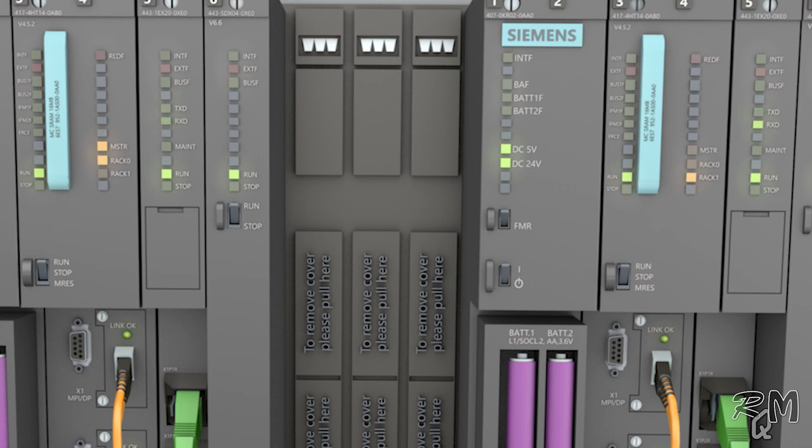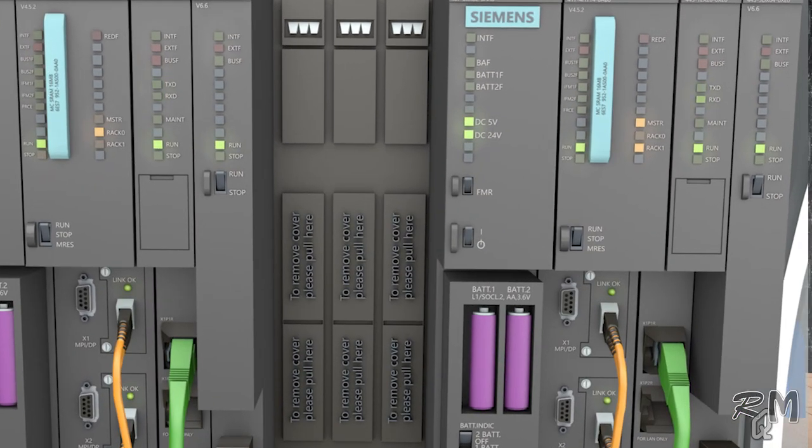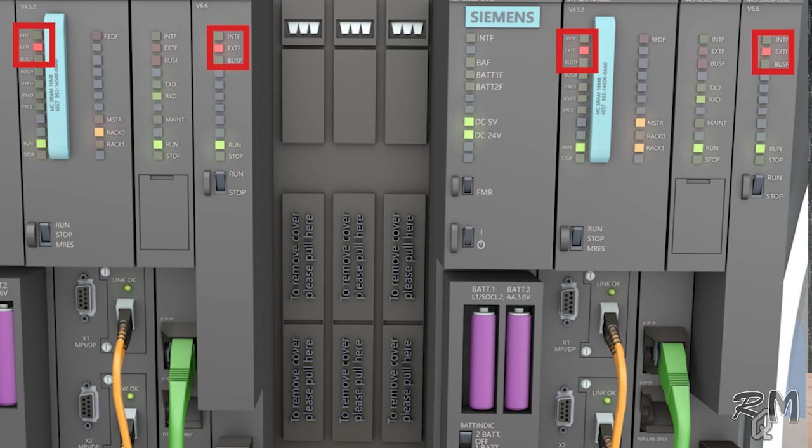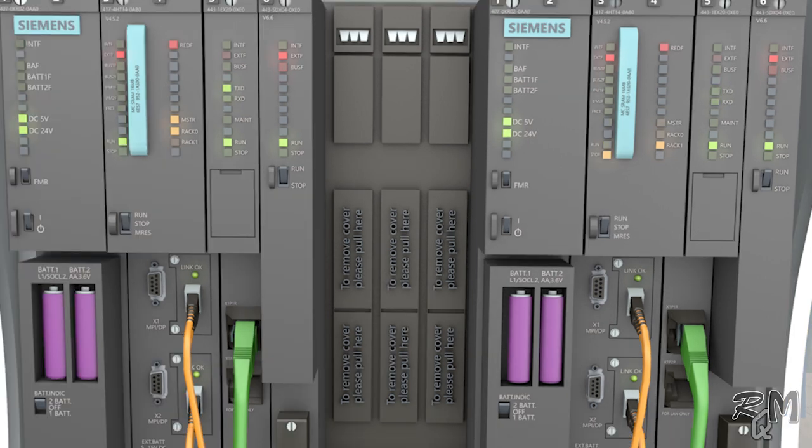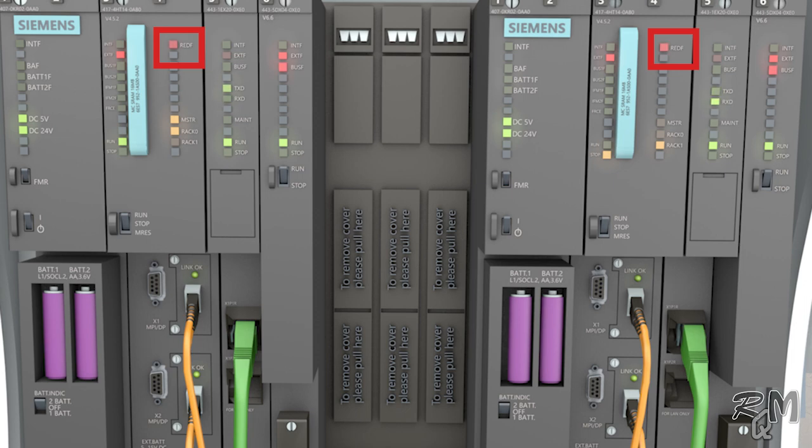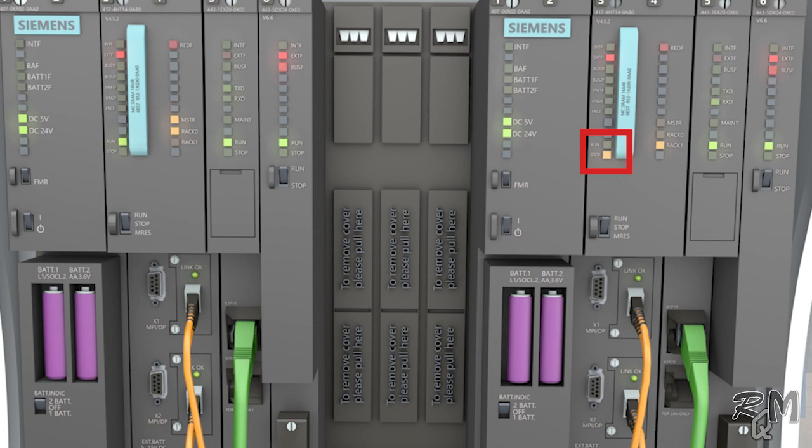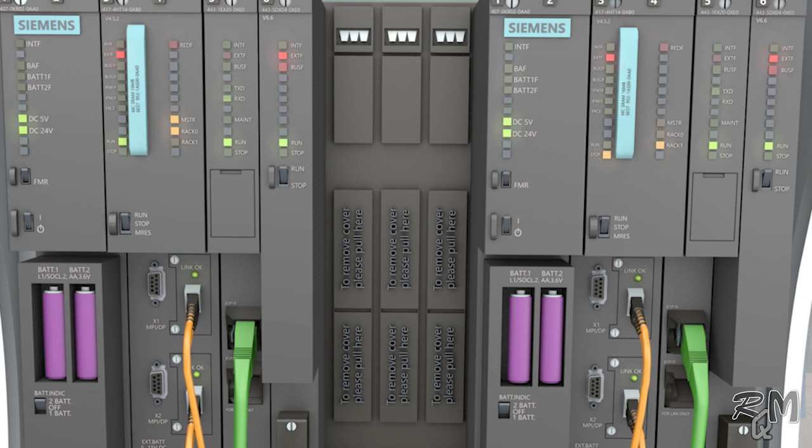Sometimes there will be external fault in CPU module and 443-5 extended module. This module is used for communication between CPU and input output cards. This external fault could be due to some fault in input or output signal so it can be ignored. In PLC redundancy loss condition you will find red F LED in on state. As you can see here both CPUs red F LED are on and rack 1 CPU is stopped but CPU switch in run position. It could be due to loss of program stored in SRAM or memory card of CPU.